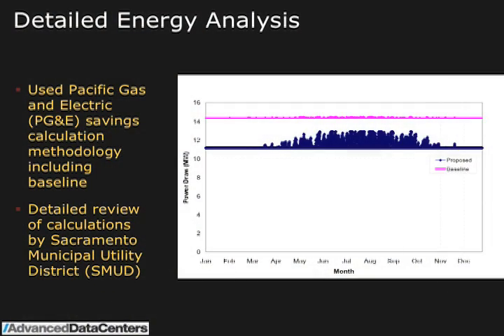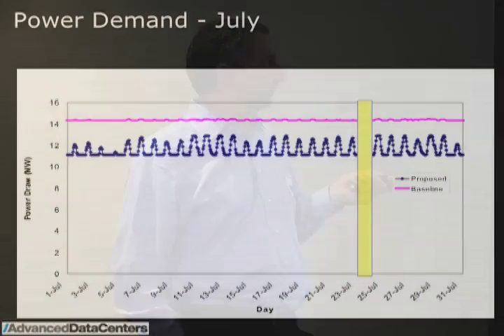So here's just a snapshot of the detailed analysis that we did for SMUD to show them the energy savings. And this is an hourly analysis of the total power draw of the facility, including the IT equipment and UPS losses and everything. And you can see in the winter months, it's flat. That's because the fans are the only thing that are running. And in the summer months, we get it bumping up here because the chiller's coming on and off. And we dug into that, zeroed in.